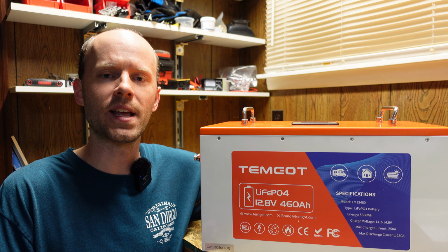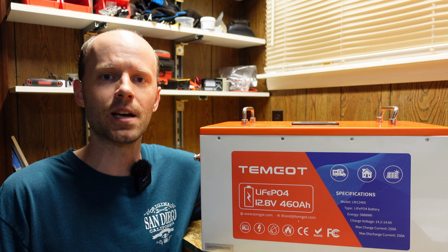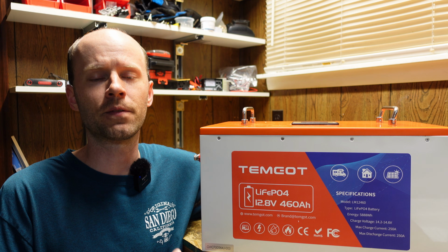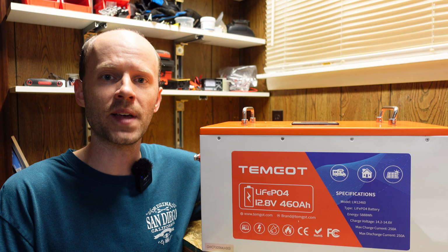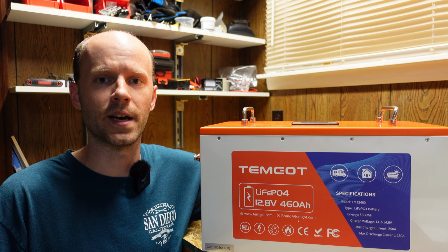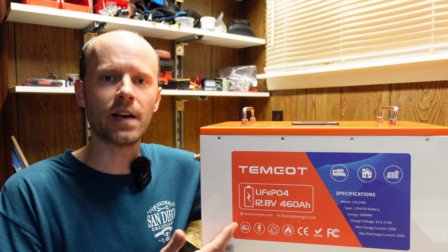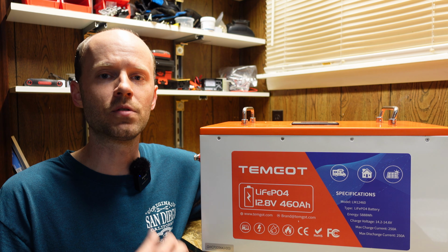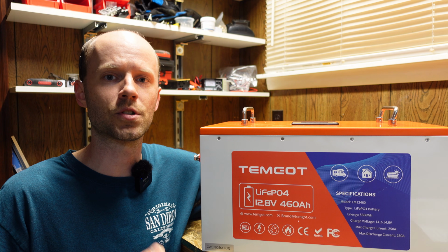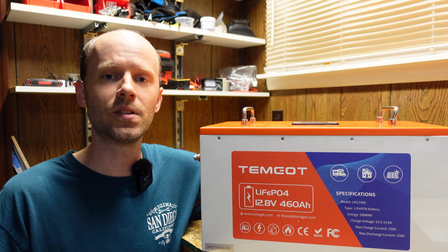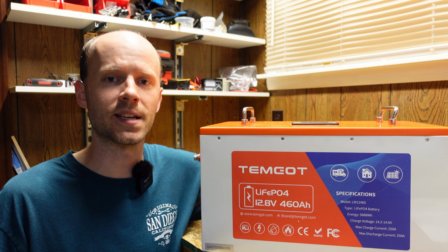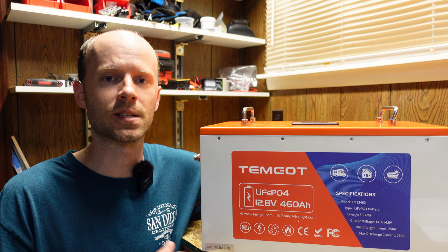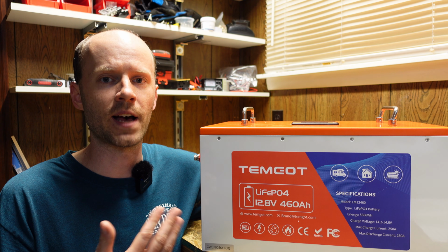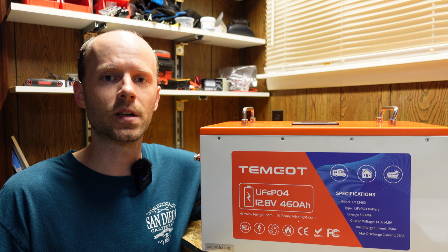This is a 12.8 volt, 460 amp hour lithium iron phosphate battery from Temgot. That's over 5,800 watt hours of stored energy. It's built in a strong heavy duty steel case and is rated for up to 250 amps continuous charge and discharge current. I haven't looked inside yet, but I already ran the capacity test, and if the inside is built as well as the capacity test performed, I think we'll have a real winner here. Let's take a look at those specifications.